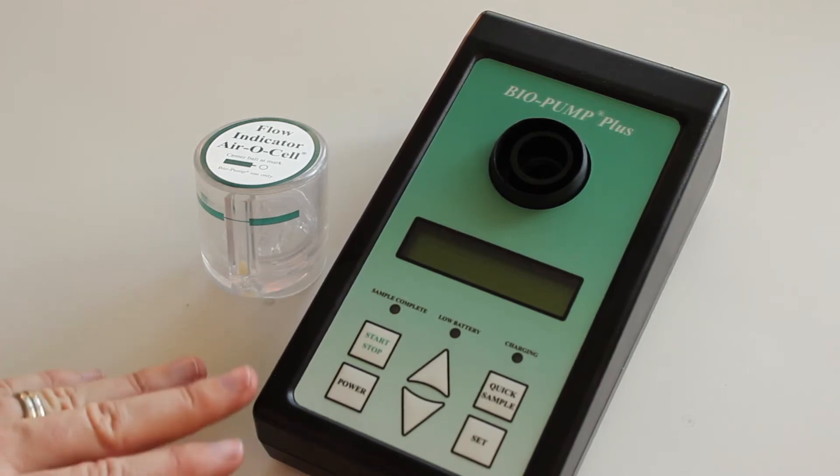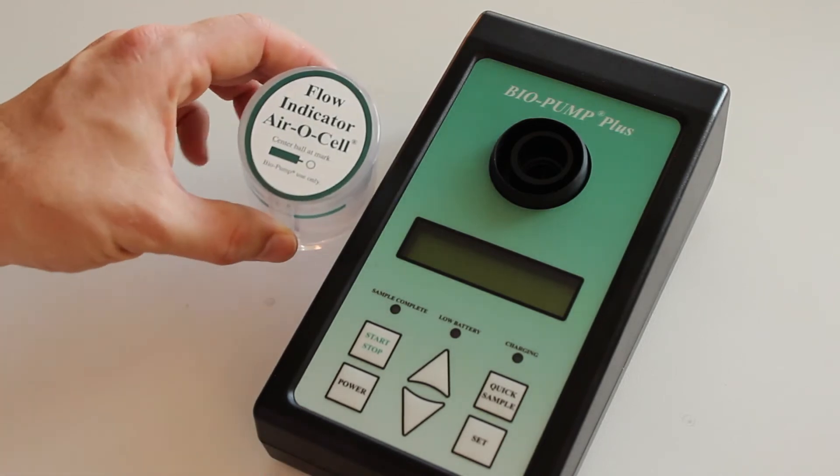You can use this for your Air-O-Cells, Allergenco-Ds and such. To check it on site you're given this flow indicator Air-O-Cell which compensates for having the differential pressure of an Air-O-Cell on there so that you get the calibration right.